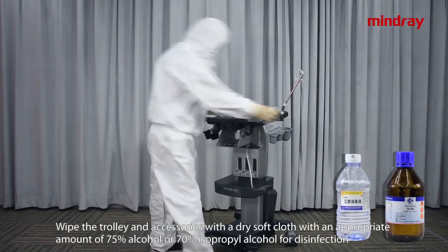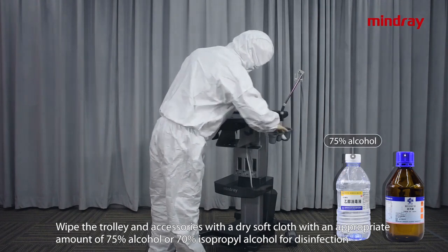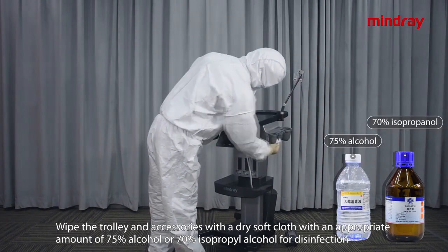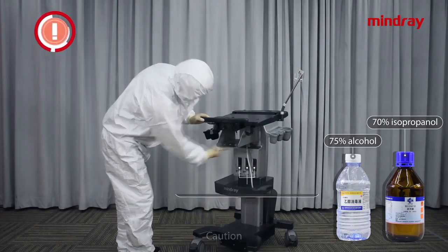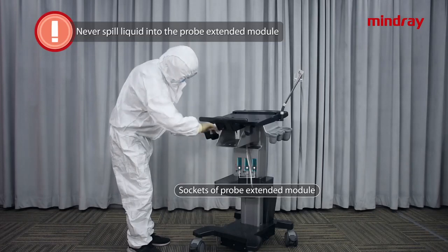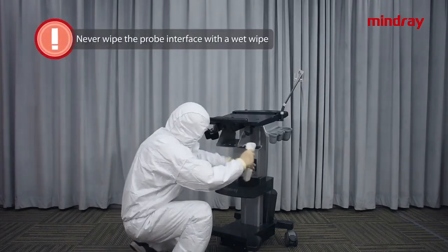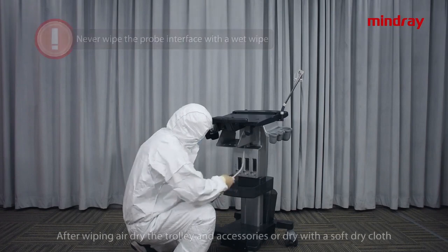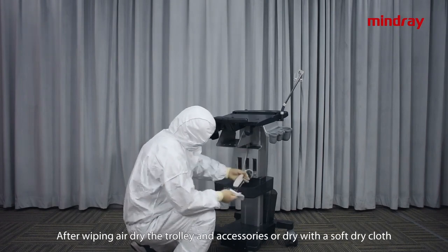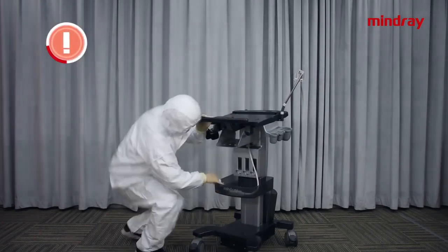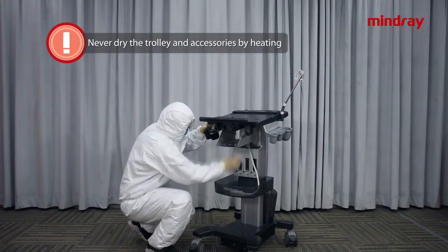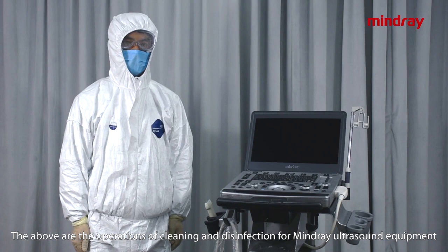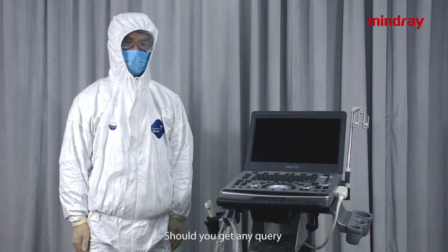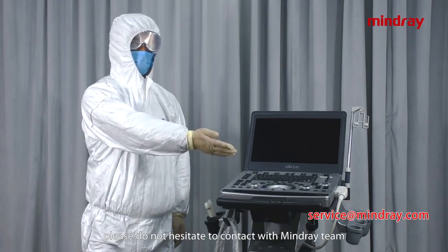Trolley and accessories disinfection. Wipe the trolley and accessories with a soft dry cloth with an appropriate amount of 75% alcohol or 70% isopropanol alcohol for disinfection. Caution: never spill liquid into the probe extended module. Never wipe the probe interface with a wet wipe. After wiping, air dry the trolley and the accessories or dry with a soft dry cloth. Never dry the trolley and accessories by heating. The above are the operations of cleaning and the disinfection for Mindray Ultrasound equipment. Should you have any query, please do not hesitate to contact the Mindray team.